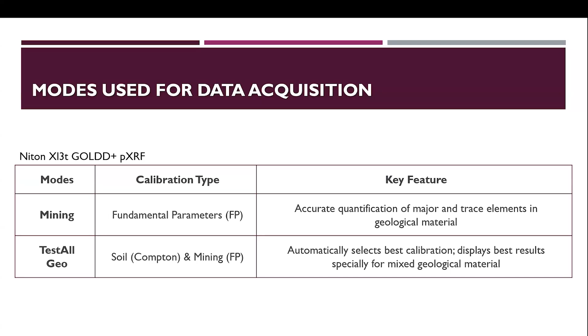Each measurement takes 360 seconds, which allows optimum time for each filter, calculated at 90 seconds for the main filter, 90 seconds for the low, 60 seconds for the high, and 120 seconds for the light elements. The duration for each filter has been tested against the errors, where for the first filter at 90 seconds, we can see that most elements can be measured with almost the same error at 60 seconds. These elements remain, however, with a lower error value at 90 seconds.